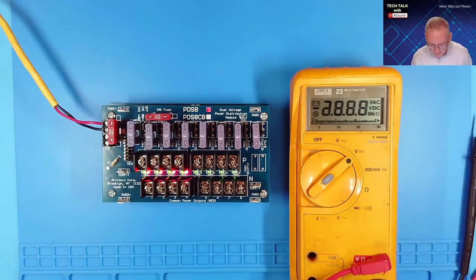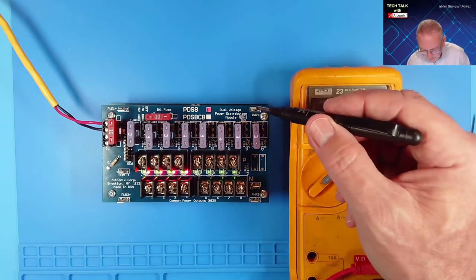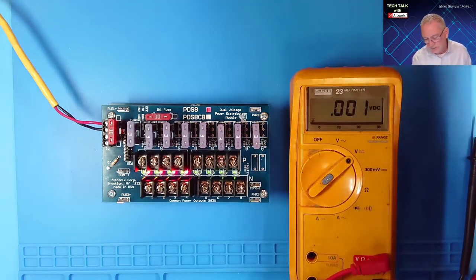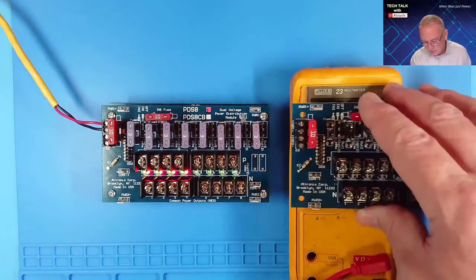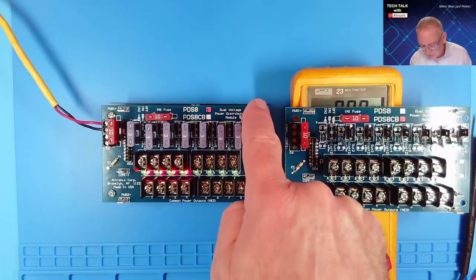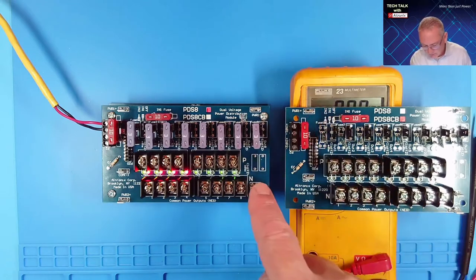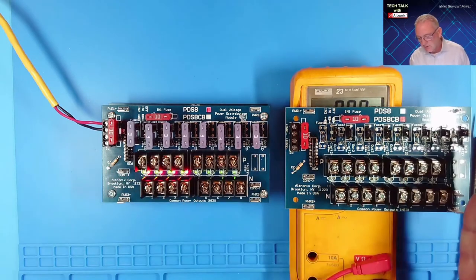So I'll point out a couple things on the board. There are spade lugs on the right and left side of the board. If we need more than eight outputs, we could add a second board by jumpering power one to power one, common to common, and power two to power two, and that would carry the power through to the second PD board.